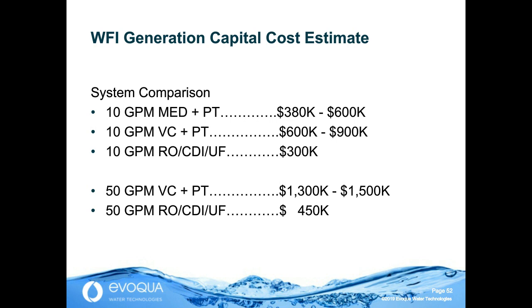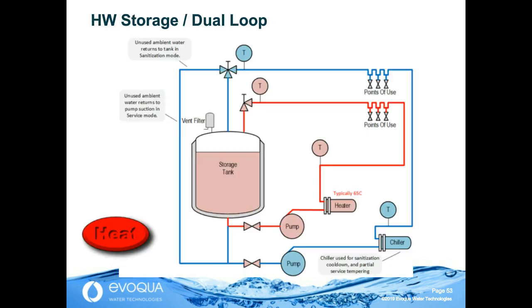We're going to talk very briefly about storage and distribution because that may be another area where membrane-based WFI systems may offer savings. There are 2 practical methods for sanitization of storage and distribution for WFI, and that is hot. Now, that could be continuous hot, and when a still is producing hot distillate, the storage is almost always continuous hot. It could be intermittent hot, but in many more cases than not, it's continuous hot storage.